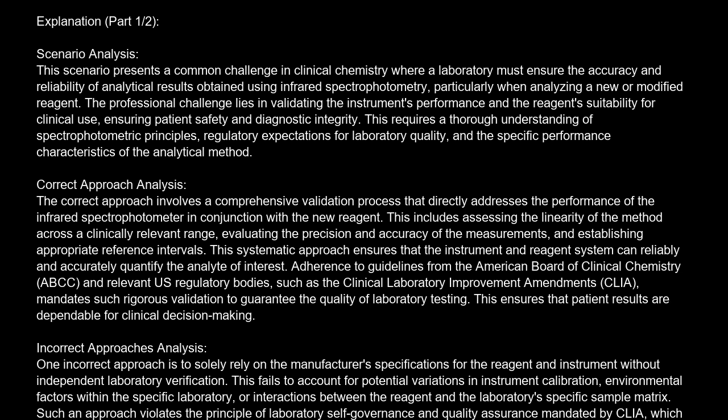Incorrect approaches analysis. One incorrect approach is to solely rely on the manufacturer's specifications for the reagent and instrument, without independent laboratory verification. This fails to account for potential variations in instrument calibration, environmental factors within the specific laboratory, or interactions between the reagent and the laboratory's specific sample matrix.